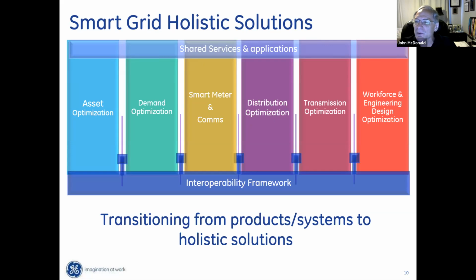If you've heard of synchrophasors or phasor measurement units, the typical data we use in SCADA, supervisory control and data acquisition, is 2-second, 4-second, 6-second data. We get operational data to the control center at most every 2 seconds, but typically every 4 to 6 seconds, maybe 10. The problem is we don't have enough granularity or detail at that sampling rate.